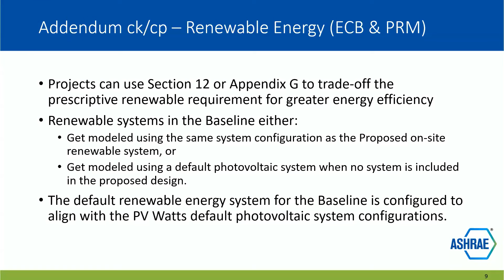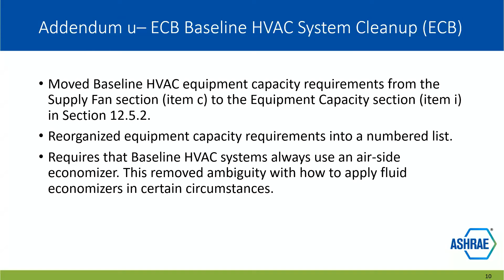Addendum U addressed 2 topics in the energy cost budget method. The first was really just a cleanup. It rearranged and moved around how the baseline HVAC equipment capacity requirements are represented in the standard. The second one was a little bit more impactful. It's how economizers are modeled in the baseline. Previously, you modeled an airside economizer in the baseline if there was an airside economizer in your proposed building design, and a fluid economizer in the baseline if there was a fluid economizer in your proposed design. Now, regardless of what is in your proposed design, you model an airside economizer in the baseline. This helped to make the modeling more consistent between different buildings.